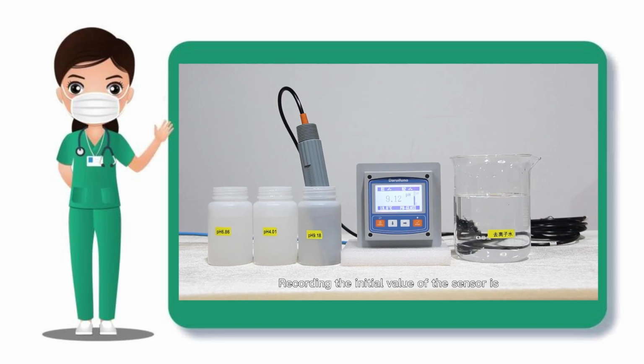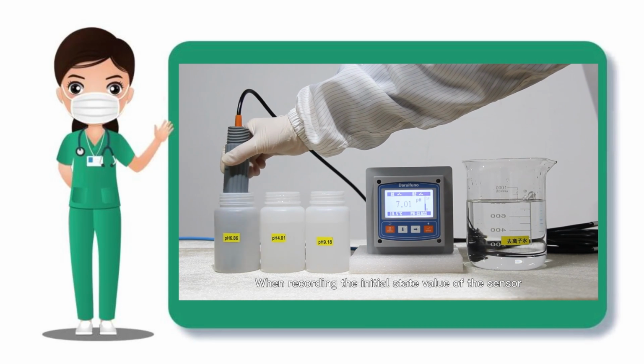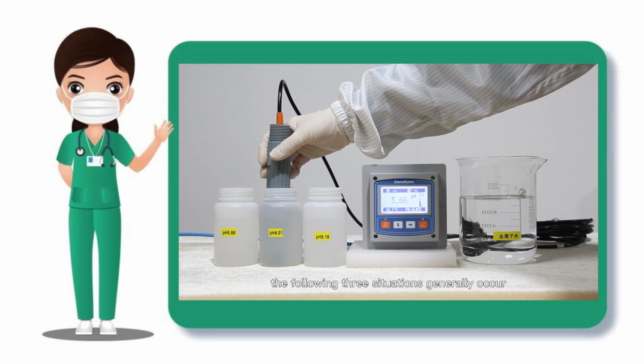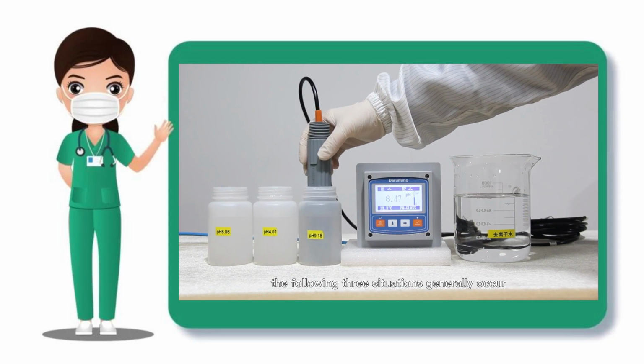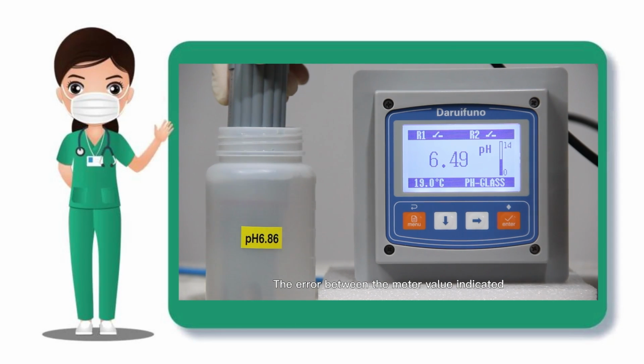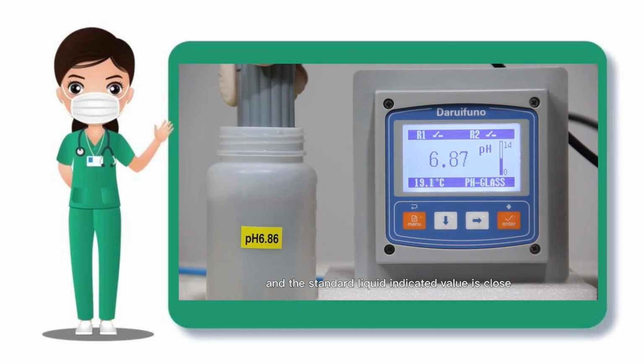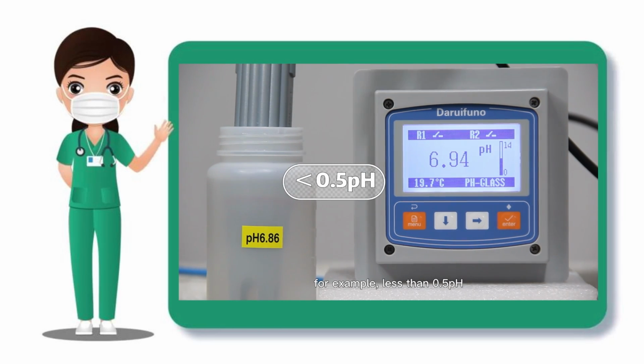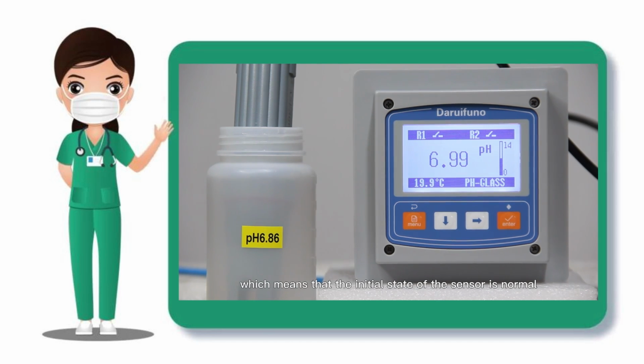Recording the initial value of the sensor is helpful to understand the initial working state and provide a basis for judging the aging process in the future. When recording the initial state value of the sensor, the following 3 situations generally occur. The error between the meter value indicated and the standard liquid indicated value is close, for example, less than 0.5 pH, which means that the initial state of the sensor is normal, and it can be calibrated immediately and put into work.